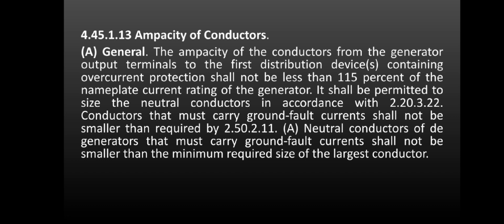Ampacity of conductors. General. The ampacity of the conductors from the generator output terminals to the first distribution device containing overcurrent protection shall not be less than 115% of the nameplate current rating of the generator. It shall be permitted to size the neutral conductors in accordance with 2.20.3.22. Size of neutral conductors. Neutral conductors of the generators that must carry ground fault current shall not be smaller than required by 2.50.2.11, that is, not smaller than the minimum required size of the largest conductor.